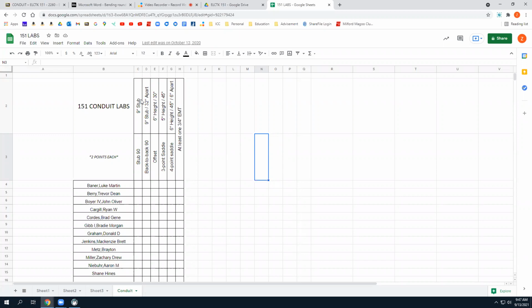But if I went like this and over, that'd be 90 plus 30 plus 30. Even better, would just be 90 and straight over. But I'm not coming from this junction box. I am coming from way down here. And that first one that I drew that had 420 degrees of bend in it, could we get that wire in there? Yeah. But eventually, the more pulling force you're pulling on that wire, you're going to start to compromise the insulation of the wire.